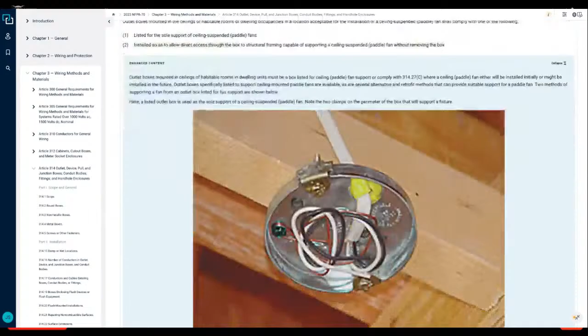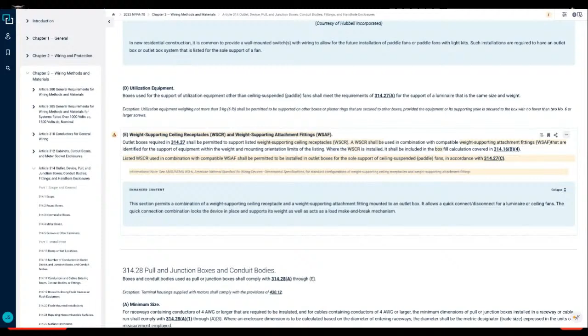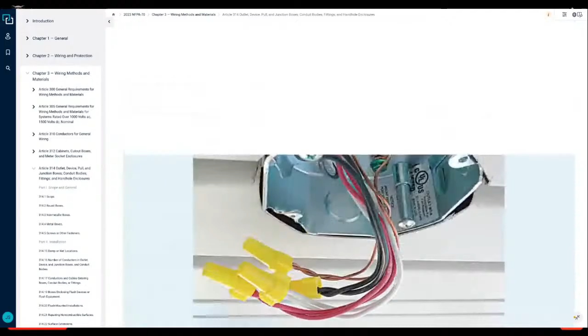Now watch this. If I look at D, it says boxes used for the support of utilization equipment other than ceiling suspended paddle fans shall meet the requirements of 314.27A for the support of a luminaire that's the same size and weight. So it takes me right back up to where I started, and it tells you in A2 that the ceiling outlets, it's a box used for that lighting or utilization equipment.